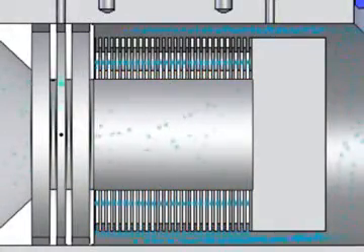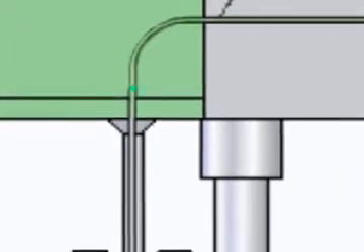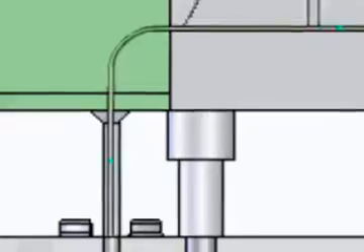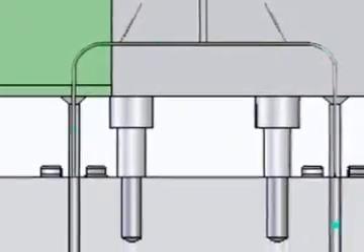This gas molecule has an important job to do. The laminar flow element generates a slight pressure drop, forcing a very small proportion of the total gas flow through Sierra's advanced platinum-wound, 316 stainless steel capillary sensor technology, where measurement takes place.